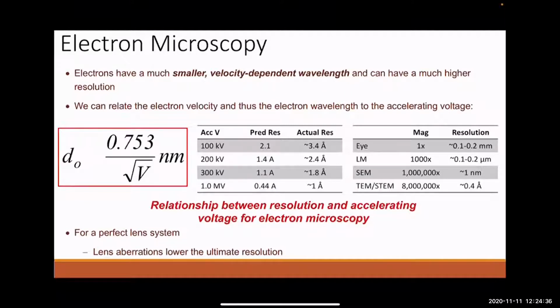And so you can see as you go to higher accelerating voltages, here's 100 kV, that's a typical TEM accelerating voltage, 200 kV, 300 kV, up to even 1,000,000 volts. That used to be a thing in the 80s, 90s. They've sort of moved away from that with the advent of aberration corrected microscopes. But the idea is that you get better resolution, as you can actually see here.